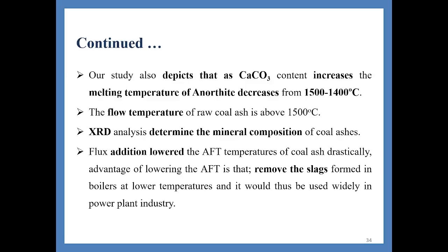And the most important thing is that XRD analysis determines the mineral composition of coal ashes. Flux additions lowered the AFT of coal ash drastically. The advantage of lowering the AFT is that it removes the slag formed in the boiler at lower temperature, and it could thus be used widely in power plant industries.